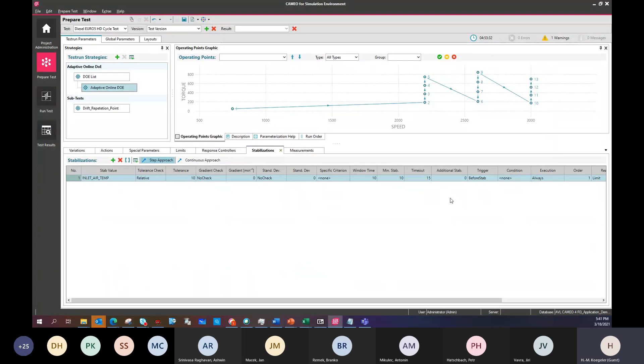It's not always the same time needed to get a certain temperature reached, and you can specify tolerances or gradient tolerances to shrink the stabilization time or to extend it until this is reached. In the variation, you specify a stop time. You see it's quite a short stop time because a stabilization criterion is used here, and the short time is elongated until these conditions defined here are reached.